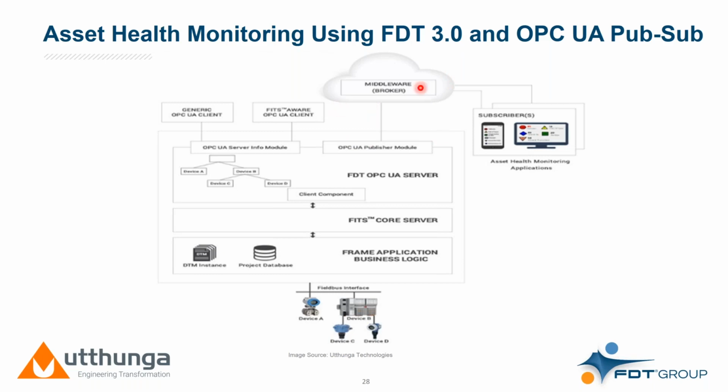Also, this publisher, which is nothing but an FDT OPC server, or anyone who has access to the devices or a data source for which we are publishing the data, and the subscriber need not have overlapping lifetimes. The publisher can just push the data to the broker and terminate. So the data will be available to the subscriber application, which can take it later. This brings a huge benefit when you want to look into the event history of what happened with the device's health status.